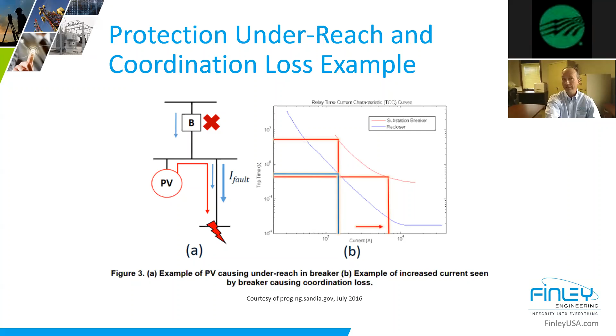So how about another example? Let's open your eyes even more. Okay, I refer to these, and others do, as sympathetic and nuisance trip examples. So let's look at my figure A. And it's kind of the same example. They just refer to it two ways. But if you look at figure A here, you've got the substation and the bus, breaker B. So normal fault current B, in blue, feeding into that fault would normally operate breaker B. But what can happen is in an adjacent feeder, or in example B, it's kind of the same thing within the feeder versus being at the substation bus level. But the point is the same, whether it's sympathetic or a nuisance operation: your PV behind its own reclosing device could cause an operation on an adjacent feeder breaker trying to feed over the bus work into that other fault on an adjacent way.